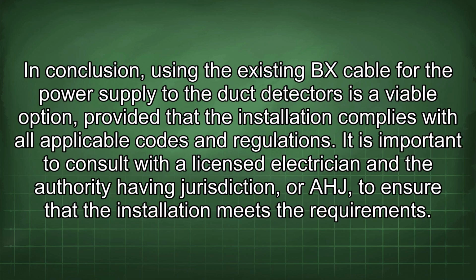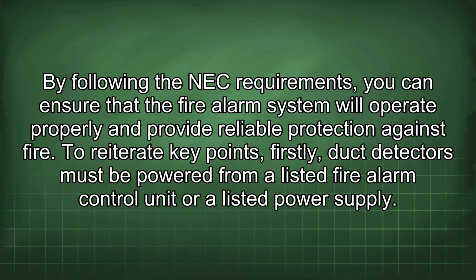In conclusion, using the existing BX cable for the power supply to the duct detectors is a viable option, provided that the installation complies with all applicable codes and regulations. It is important to consult with a licensed electrician and the authority having jurisdiction to ensure that the installation meets the requirements. By following the NEC requirements, you can ensure that the fire alarm system will operate properly and provide reliable protection against fire.